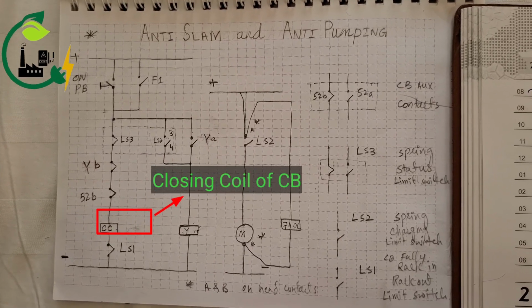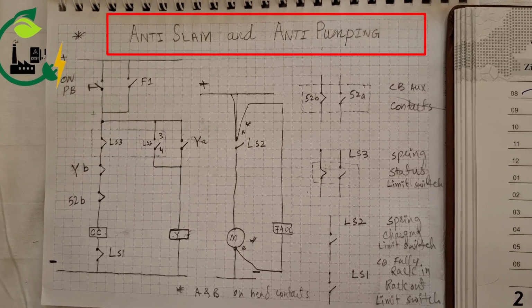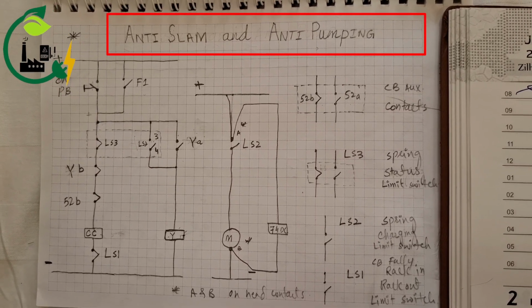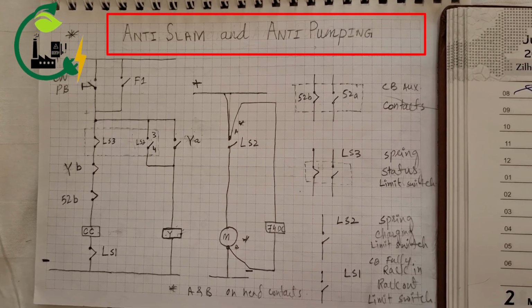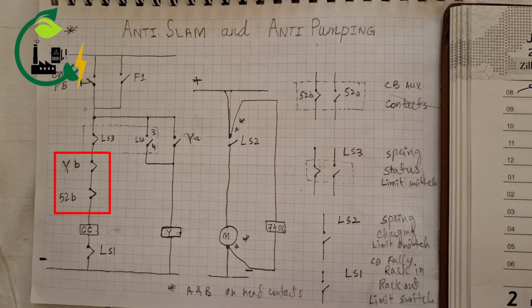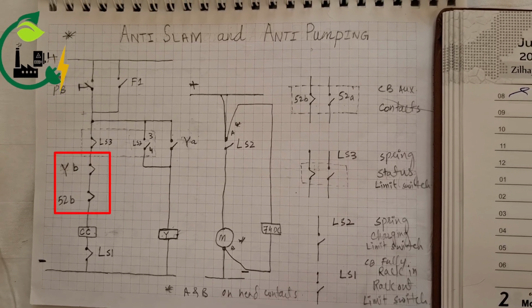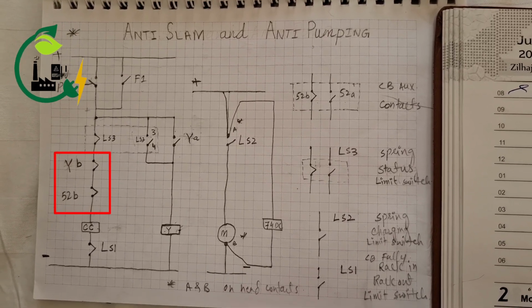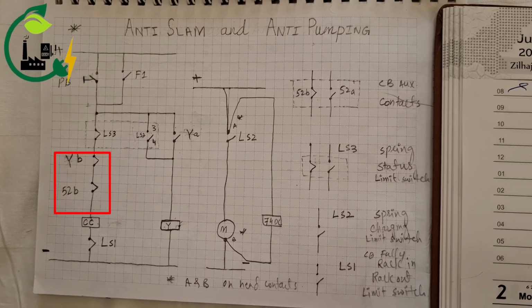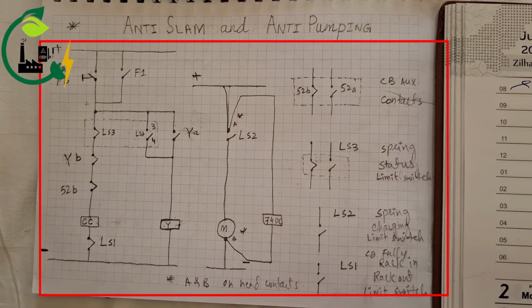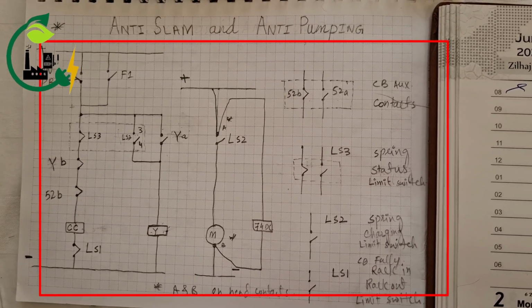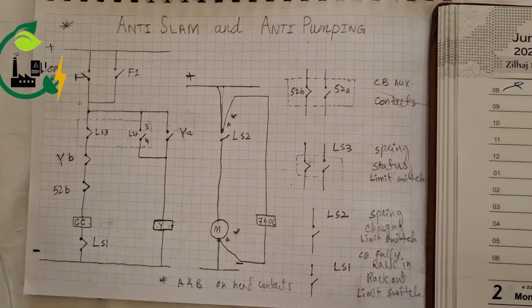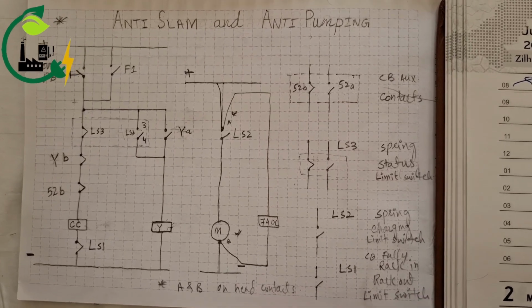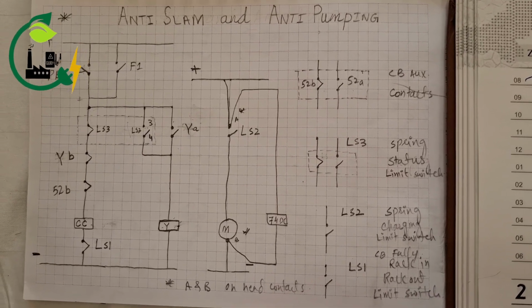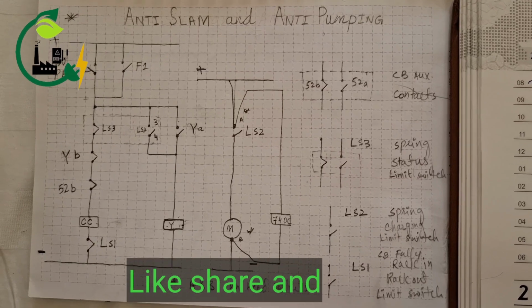I hope you understand the anti-slam and anti-pumping relay in detail. So 52B is the anti-slam contact and YB is the contact of the anti-pumping relay. This is the common closing circuit of any circuit breaker. These anti-pumping and anti-slam relays are always used in the closing circuit of circuit breakers. You can check in your schemes.